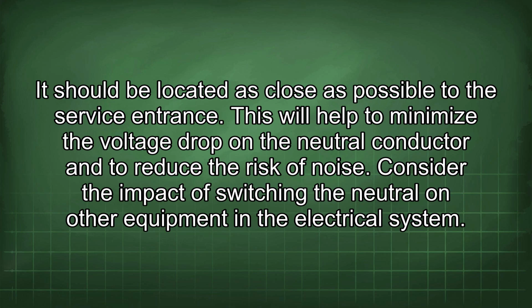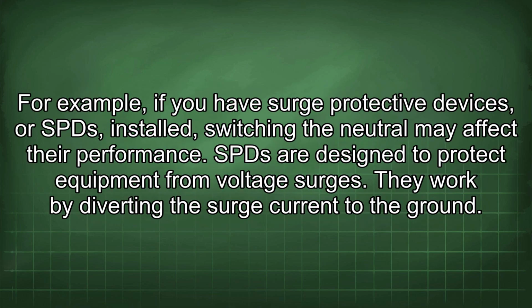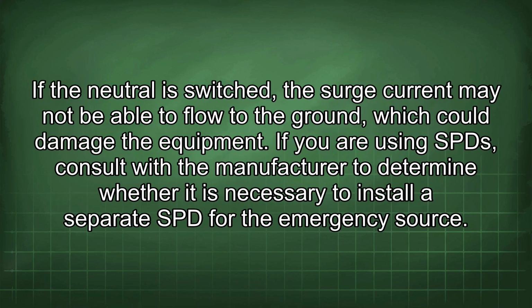Consider the impact of switching the neutral on other equipment in the electrical system. For example, if you have surge protective devices or SPDs installed, switching the neutral may affect their performance. SPDs are designed to protect equipment from voltage surges. They work by diverting the surge current to the ground.